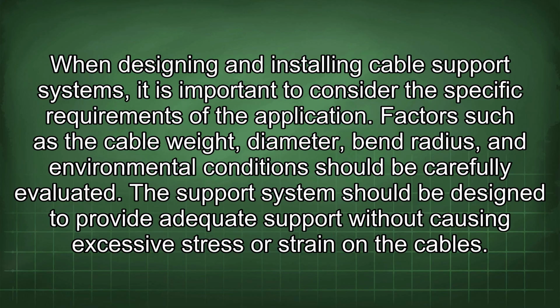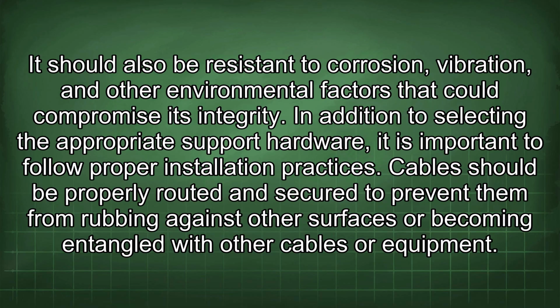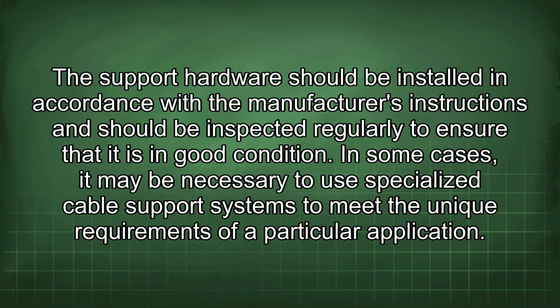The support system should be designed to provide adequate support without causing excessive stress or strain on the cables. It should also be resistant to corrosion, vibration, and other environmental factors that could compromise its integrity. In addition to selecting the appropriate support hardware, it is important to follow proper installation practices. Cables should be properly routed and secured to prevent them from rubbing against other surfaces or becoming entangled with other cables or equipment. The support hardware should be installed in accordance with the manufacturer's instructions and should be inspected regularly to ensure that it is in good condition.